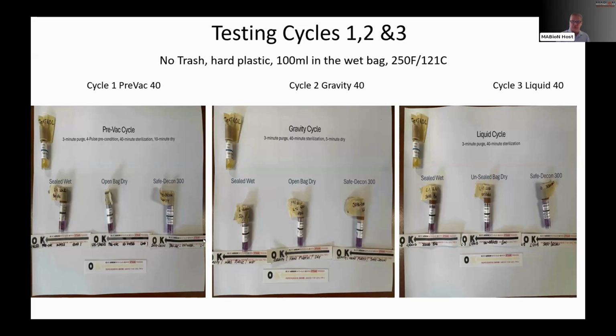So then I decided, I said, okay, let me run a gravity cycle the same way. It was the same identical setup, 3-minute purge, 40-minute sterilization, a 5-minute dry at the end on the gravity. Same, no trash, 1 piece of hard plastic in the bag. This bag was open. This bag was sealed wet, and it ruptured again during the process.